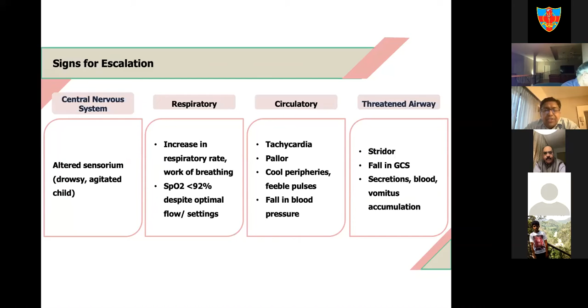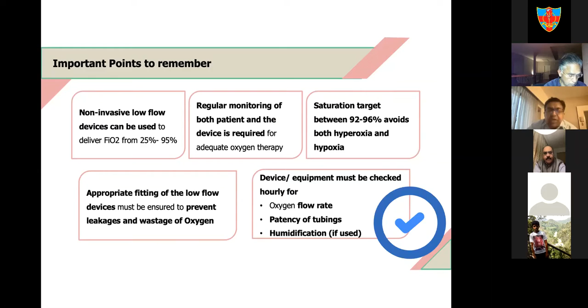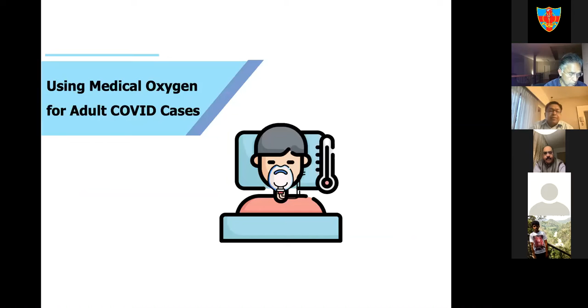Now, whenever we initiate these devices, you need to have good monitoring. They should be monitored regularly, maybe hourly, or continuously. They should be monitored for the oxygen flow rate, the patency of the tubings, the leakage from these areas, and humidification. It is very, very important to monitor all these aspects so that we can bring down the oxygen flows as per the patient's requirement and response, and we are not wasting oxygen unnecessarily.